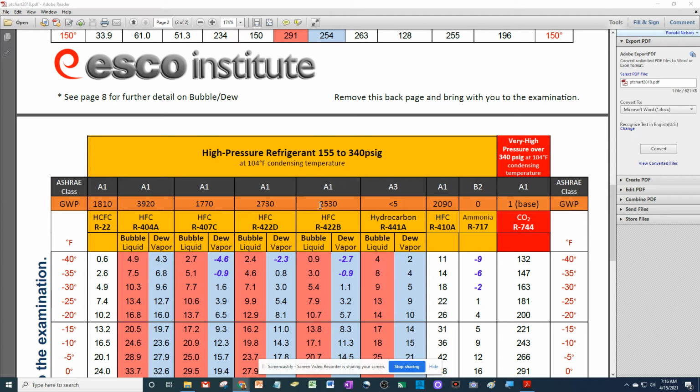And then you could answer questions like, if it's a high pressure refrigerant like 410 and it's less than 200 pounds, then the vacuum rate for that refrigerant, if it's less than 200 pounds, would be what? 0, right? But if it was more than 200 pounds, the answer would be 10. So see how this, okay, it told me it's a high pressure. So less than 200, it's a 0, and more than 200, it's 10 inches of vacuum, all right?